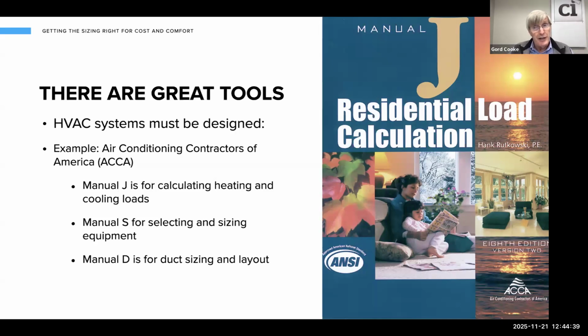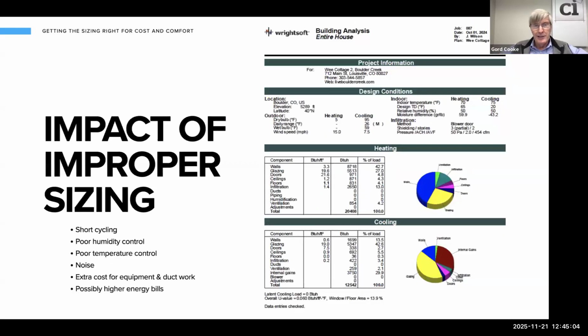Important out of that, though, is to get credit for that, to do a proper heat loss, heat gain. Hopefully, new construction builders are doing this, but even if some of you are doing replacement work, renovation work, you should be doing these calculations. And there is an association, the ANSI Association and ACCA, Air Conditioning Contractors of America, that provide the software that allows you to do proper heating and cooling. And I'll highlight a couple of those issues. There is the output from, you don't need to read the numbers. It's just showing you the output. It gives you a sense with the graphs, with the pie charts, where the energy is going.